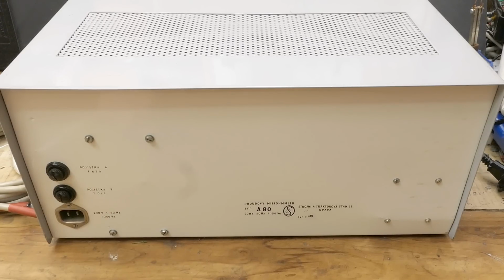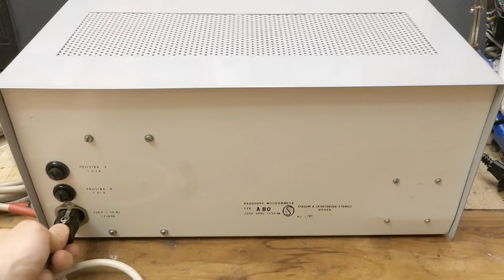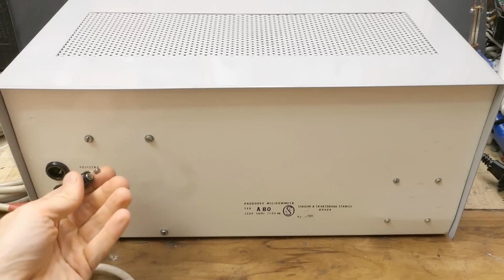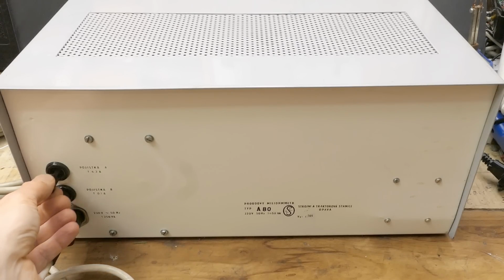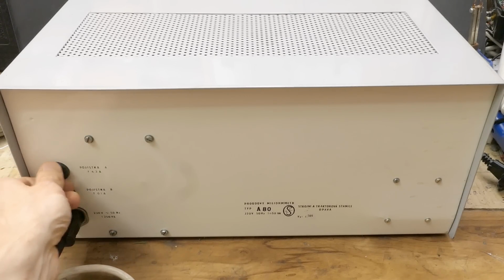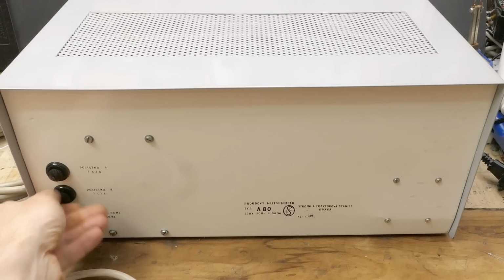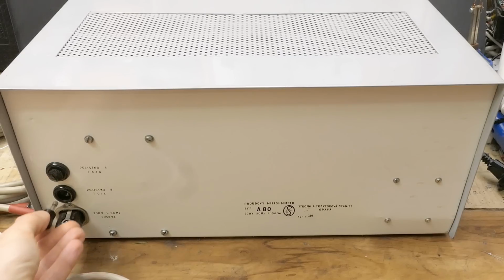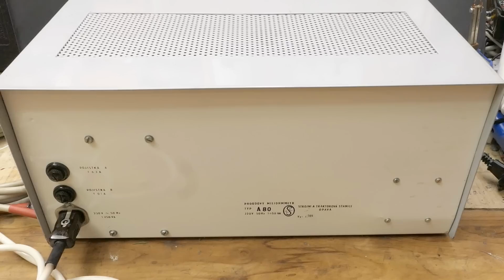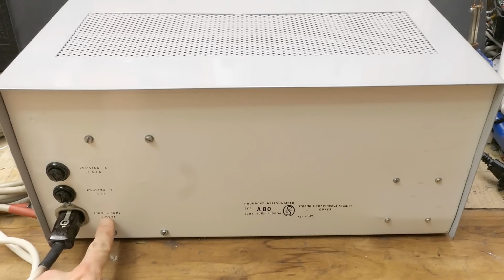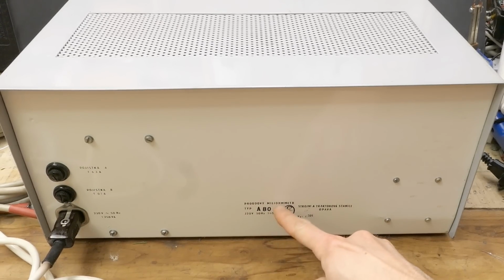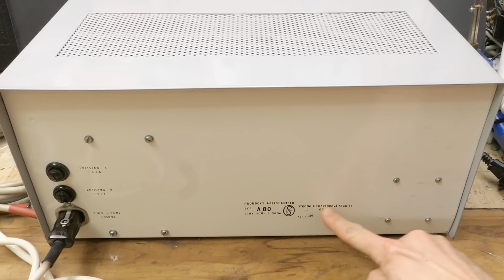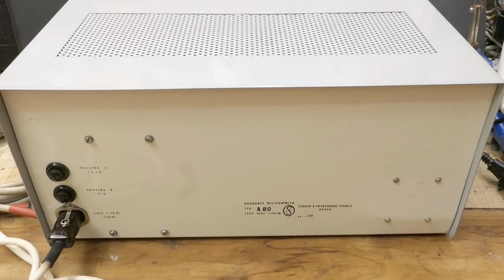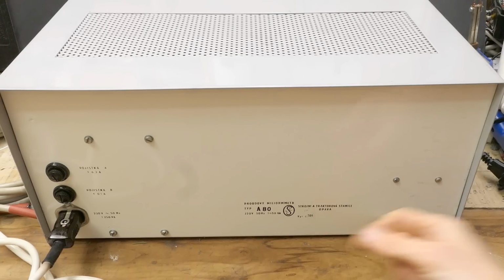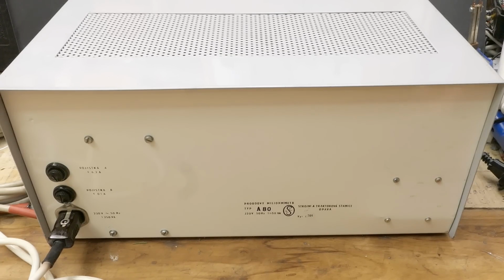Now let's take a look at the back panel, not that much to see here. This plug goes in here, there are 2 fuses with screwable covers, they seem fine. And this one says fast 6.3 amps, and it actually is fast 6.3 amps, something you don't see very often, and this one is 0.1 amp slow, and it actually really is 0.1 amp slow. I almost can't believe it. And it says 1250 bloody volt amps, basically to measure the resistance of something. This is bloody amazing. Current milliohmmeter, made in a machine and tractor station, Opava City in Czechoslovakia, probably in the 80s. And some series number looks like 249, and they probably made just a couple hundred of these.